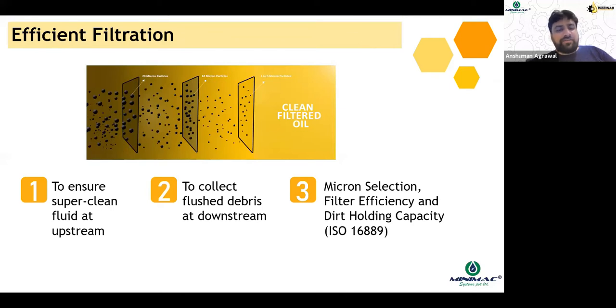Why do you require filtration at the downstream of flushing? Because after flushing, a lot of debris gets added to the fluid which is used as the flushing fluid. And this debris needs to be collected before it recirculates in the same pipeline. So you require filtration on the upstream, where you are charging the fluid into point A of your loop, and you require efficient filtration at the downstream of the flushing loop. And how do you do this filter selection?